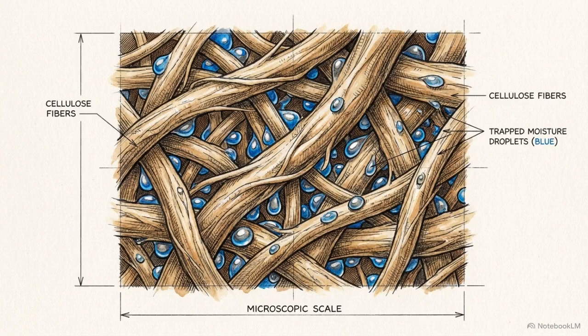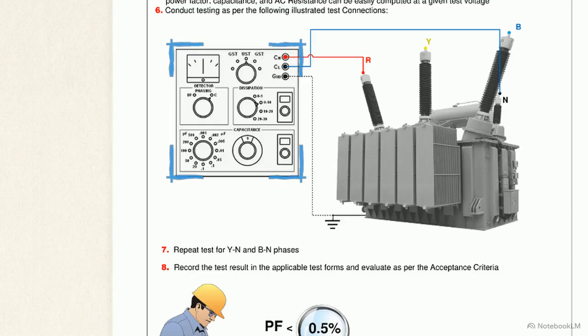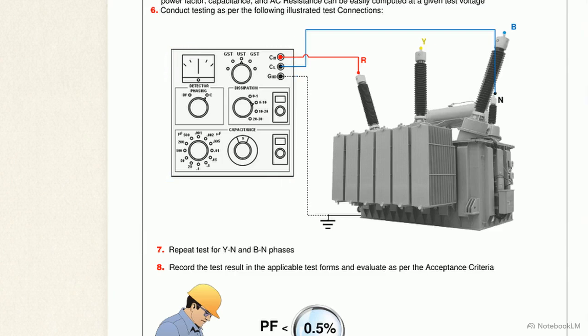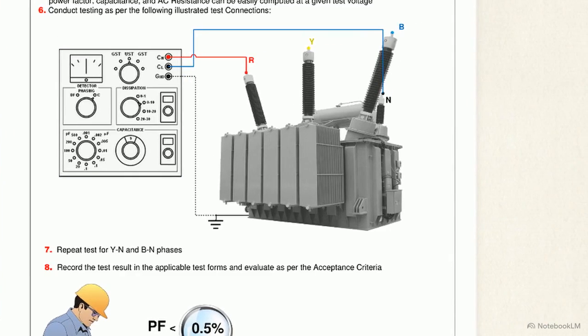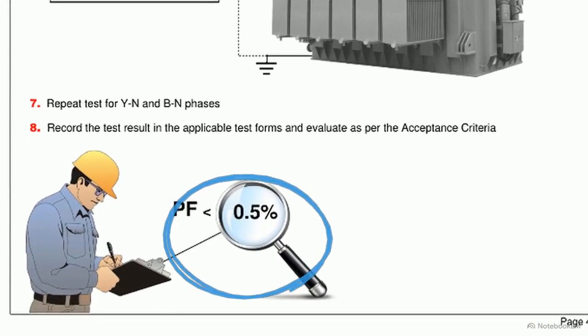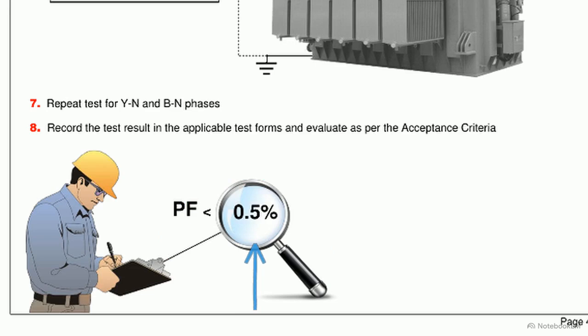Standard Megger testing evaluates gross insulation integrity, but it cannot detect microscopic moisture in the cellulose paper or subtle chemical contamination in the insulating fluid. This panel illustrates the Doble power factor, or tan delta, setup. We apply a 10 kV alternating current to the terminals and measure the slight capacitive charging current and watts loss leaking through the insulation. As highlighted by the magnifying glass, the acceptance criteria is exceptionally tight. A power factor exceeding 0.5% requires an immediate investigation into the transformer's internal state.